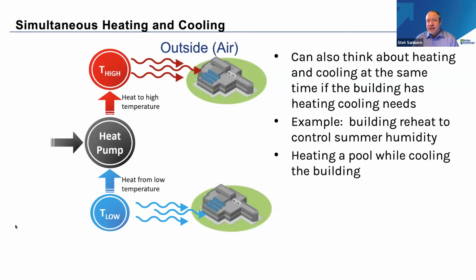In the best case, though, heat pumps can actually be used in what we call simultaneous heating and cooling mode. This typically happens in larger buildings where some portion of your building is heating and some portion is in cooling mode. This can also occur if you are in a very hot, humid climate, but you also need to heat a pool or heat domestic hot water. Simultaneous heating and cooling actually uses both sides of that heat pump. On one side, I steal the heat to make, say, my pool warm or domestic hot water warm, while the other side, the cold side, is providing simultaneous cooling in the building. This is the best case of both worlds. I'm getting heating and cooling and using both sides of that effectively within my building.